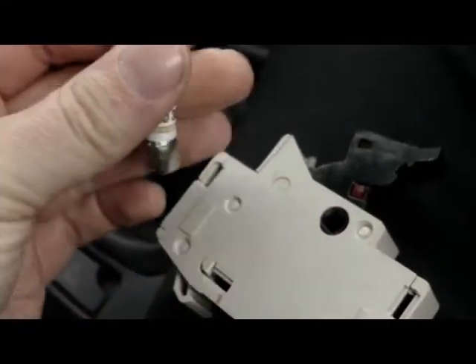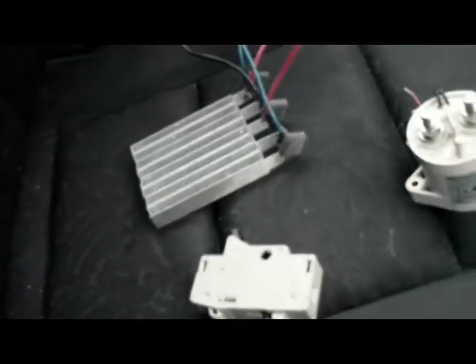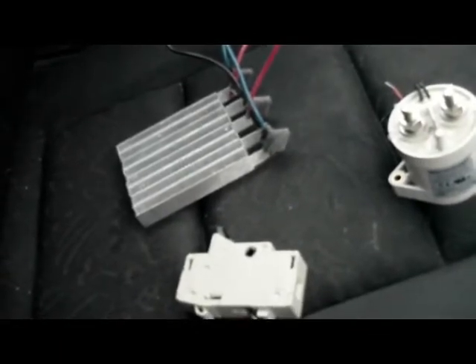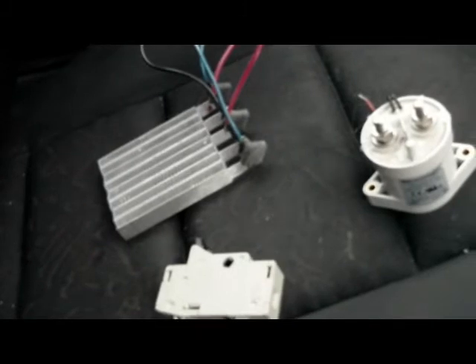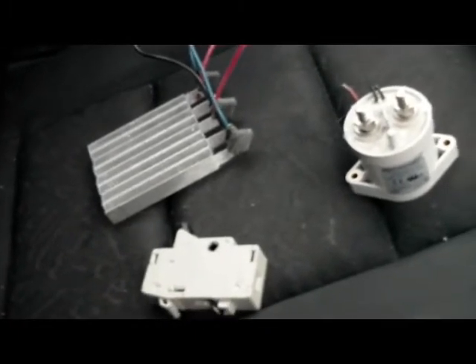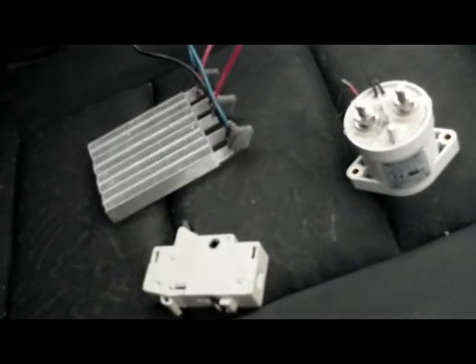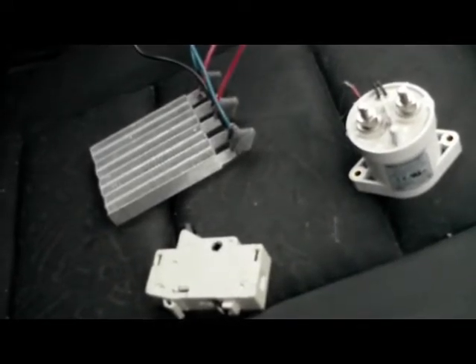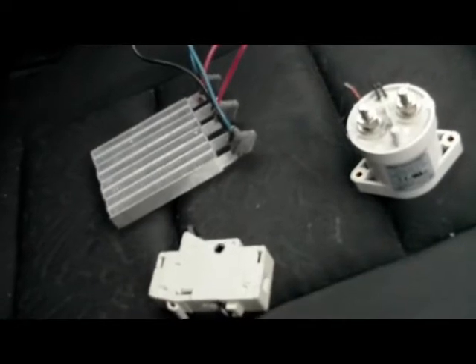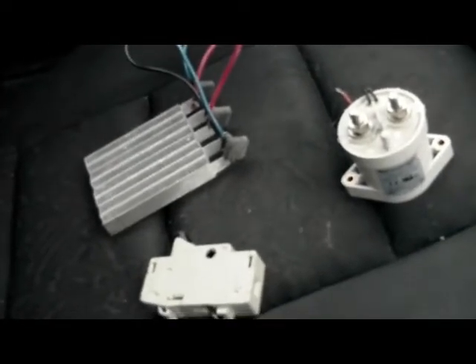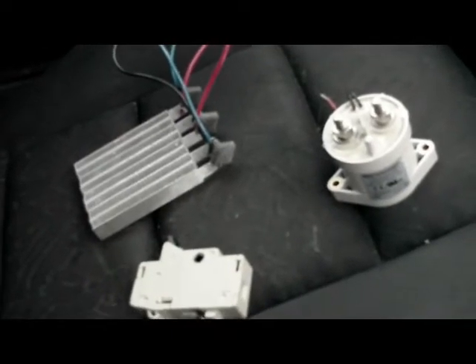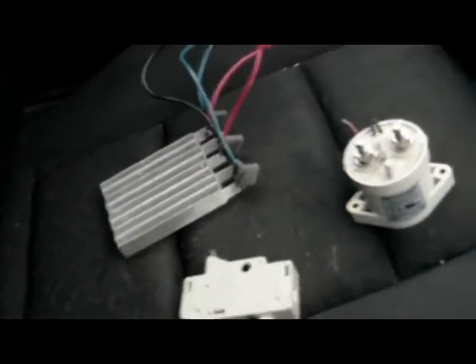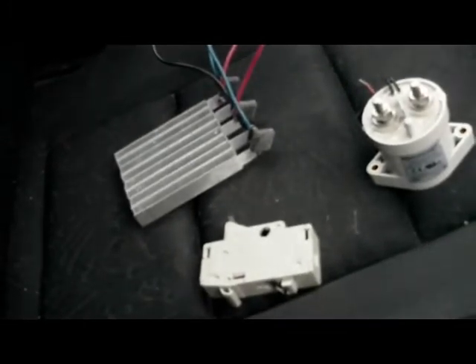Now, as I've said, some people seem to have difficulty with the starting surge on those ceramic heaters. I haven't seen that—maybe it's just the way I've set it up, but I haven't had a problem. Yes, there is a current spike when the contactor comes in, but there's a 30 amp fast blowing fuse in there, and it doesn't cause any difficulty.